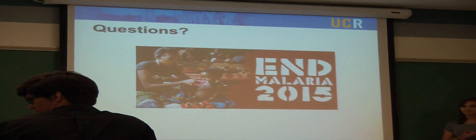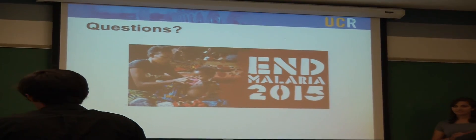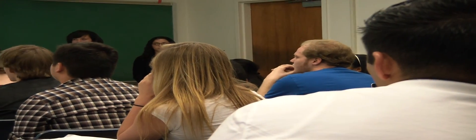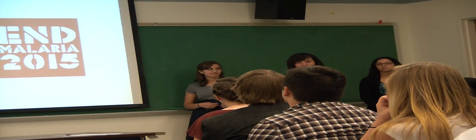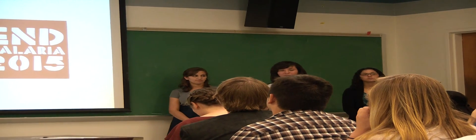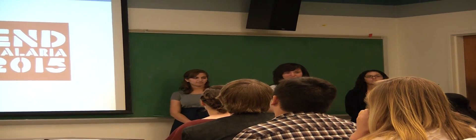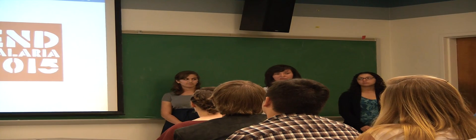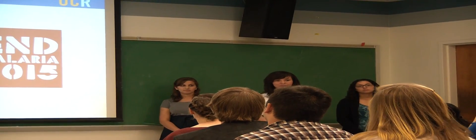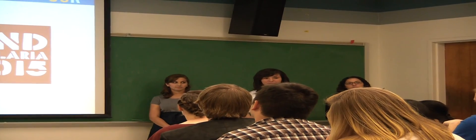We have about three and a half minutes for questions. Are the lab chips reusable or is it a one-time test? There's different designs. Some are designed so that you can reuse them, but that has a lot of problems because blood could be contagious. Most of them, because they cost so little, it's more efficient to just use one each time. But the reader, that one you do reuse. That's the initial investment.